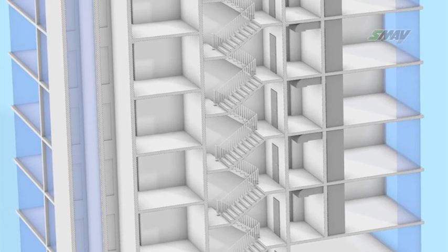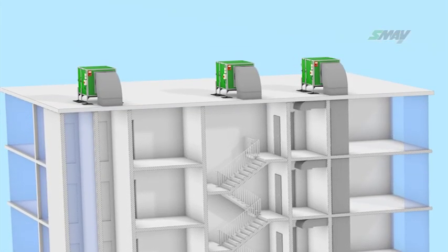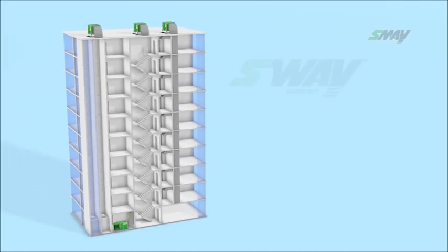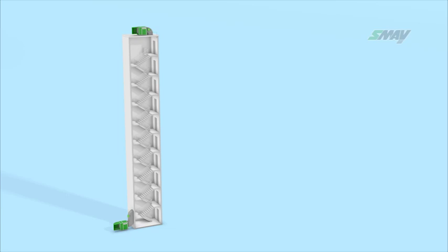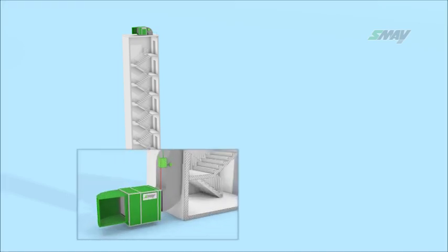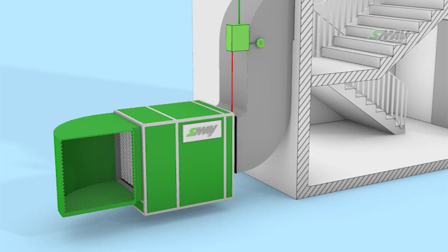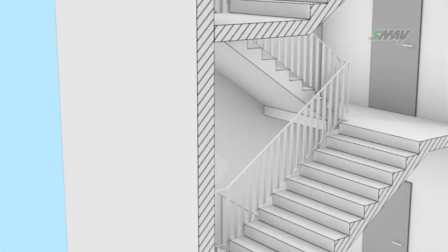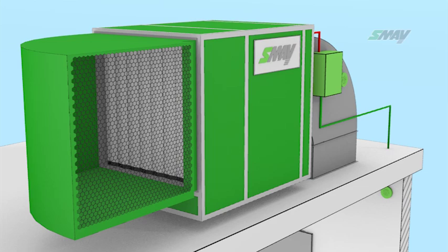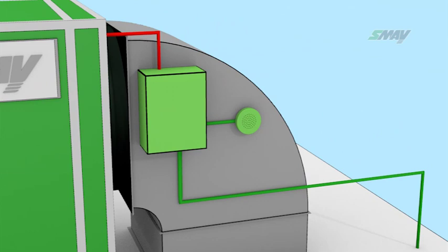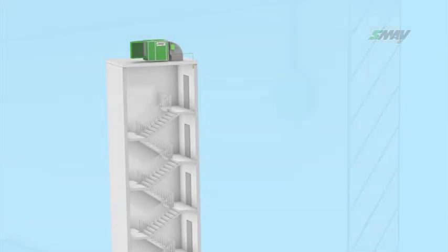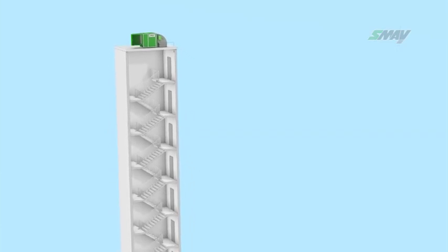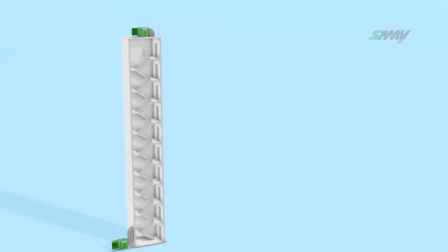Regardless of the required PDS pressure differential system class, SME suggests using the Safety Way pressure differential system. The basic version of the system comprises two reversible flow fans located at the extreme floors of the stairwell. The fans work in opposite directions — when one delivers air to the stairwell, the other extracts it. The fans are equipped with motorized air dampers operating as pressure controllers and a regulation automation system, creating a volume inside the stairwell of controlled airflow at a controlled intensity, resulting in a stable distribution of static pressure across the entire stairwell.